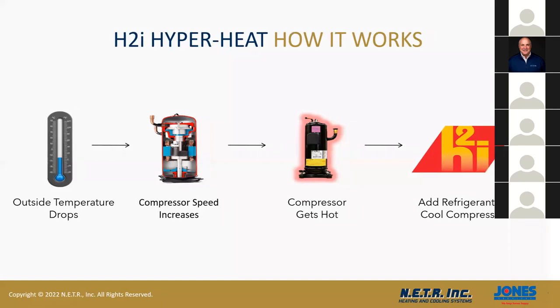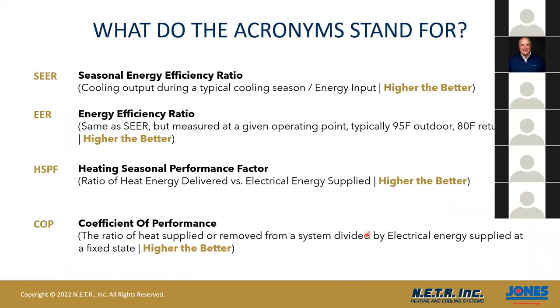So when we look at heat pumps and we're looking at purchasing a heat pump, there are some acronyms you need to know. You see a lot of these acronyms when you go to buy a washer, a dryer, a refrigerator, an air conditioner, whatever, but sometimes you really just don't know what they mean. The SEER is the SEER rating, okay? And if there's one thing you take from this slide, I just want you to know that higher is always better, all right? So the SEER rating is the cooling output during a typical cooling season divided by the energy input. The higher the SEER number, the more efficient it is, okay? A basic SEER rating that you have to have in the United States right now is 13 SEER. The manufacturers cannot make anything less than 13 SEER.